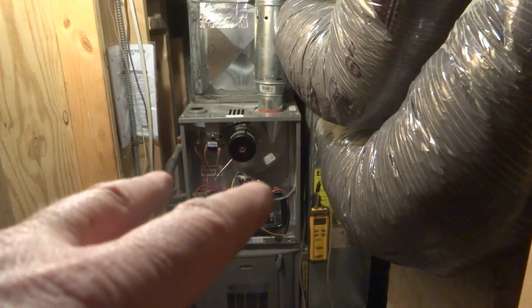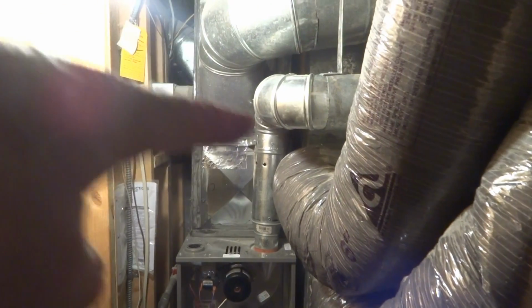Tara, check the gas pressure on this and check the combustion analysis. I got two ports in there, 3.5. I'll put the door on it. You can see I'm going out there with the thing. We'll see if it changes with the door - shouldn't change.